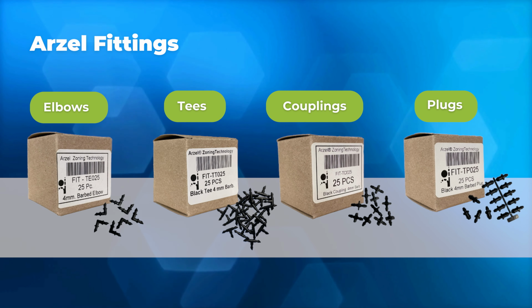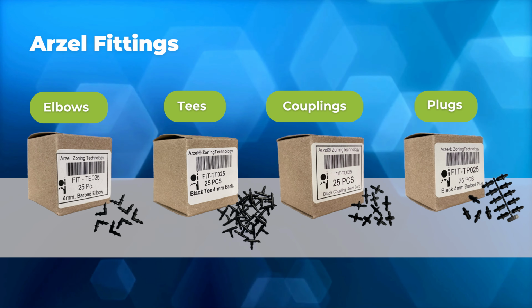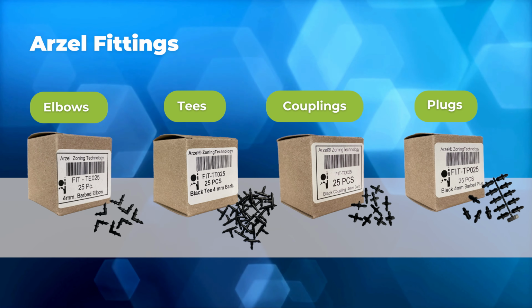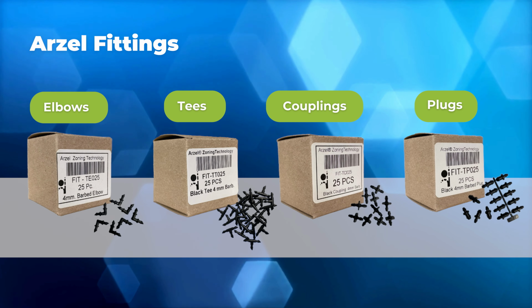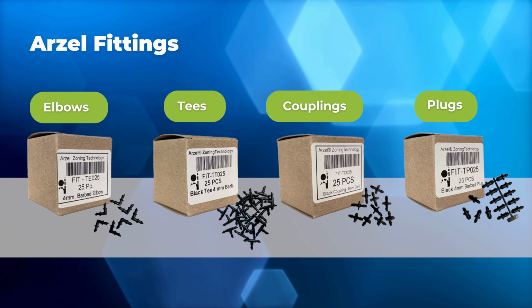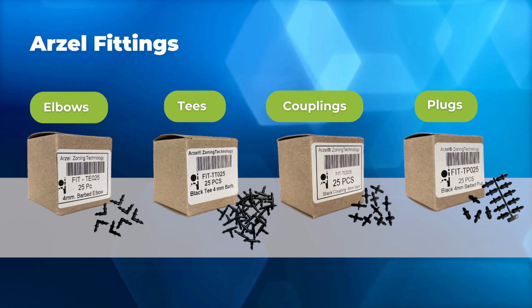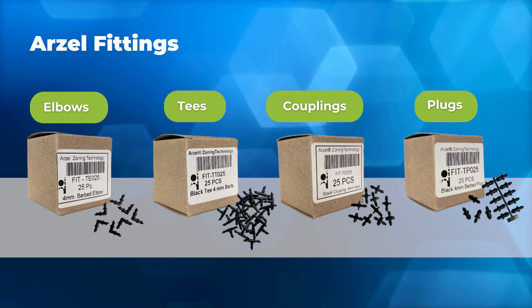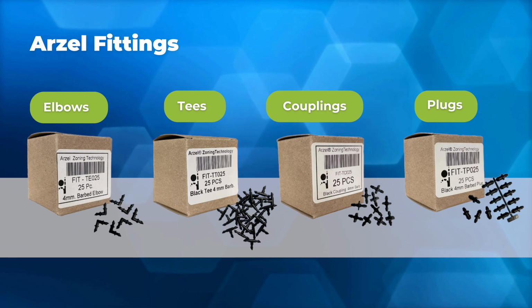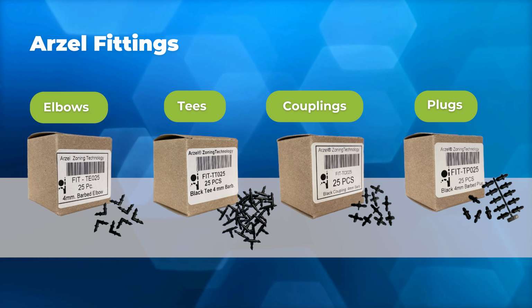And then the next fitting there is going to be our barbed plugs. These you're never going to use on an installation. They're more so for troubleshooting. If you do a lot of Arzel or you run into our panels a lot, I would have a box of these on your truck if you ever have to troubleshoot a leaking damper or something like that. It really speeds up the time on diagnostics.